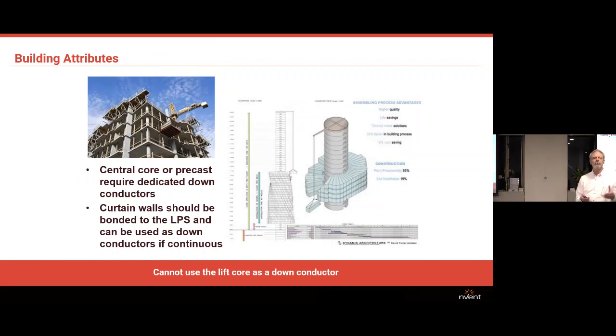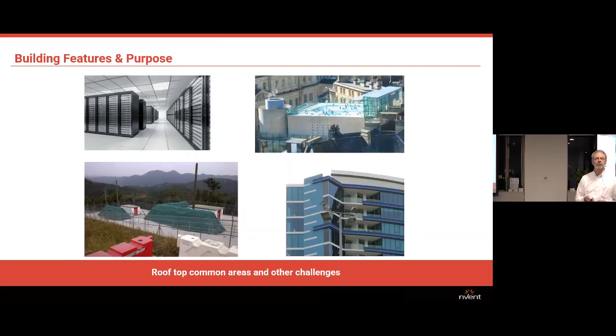This does mention building attributes a little bit, and challenges they may provide. So if you've got a building with a central core and the lift runs up the central core, and perhaps you've got a glass outer, it's difficult to run down conductors around your outer, so that can be a challenge complying with the lightning protection standard. You can't run down conductors up the lift well either, that sort of thing, so that's another restriction on using the inside. It does say here that curtain walls could be bonded to the lightning protection system and can be used as down conductors if continuous, so that's an opportunity.